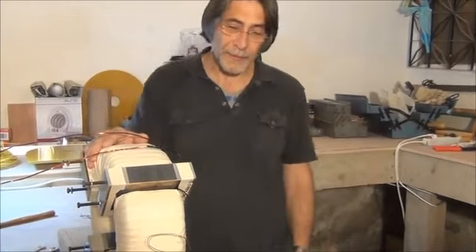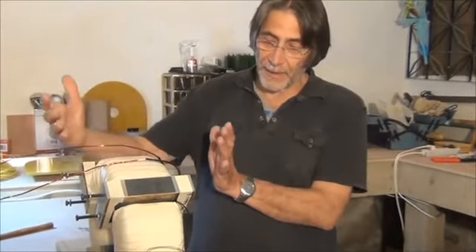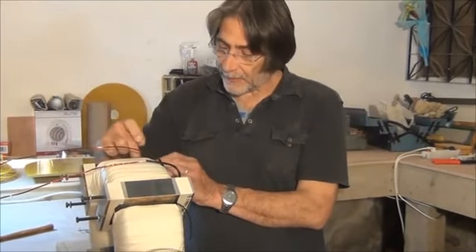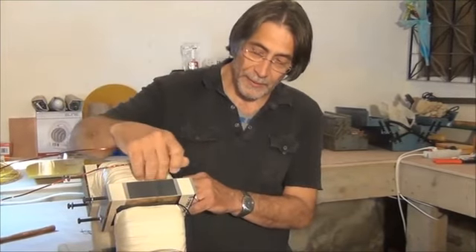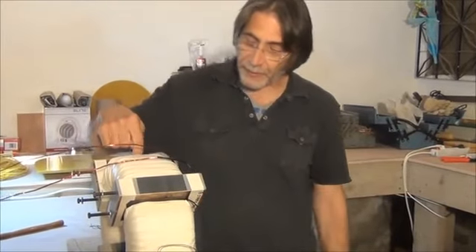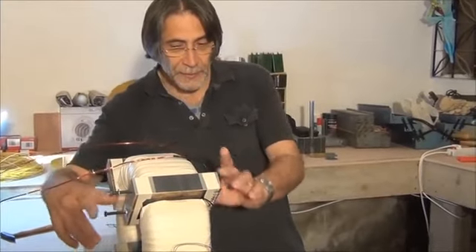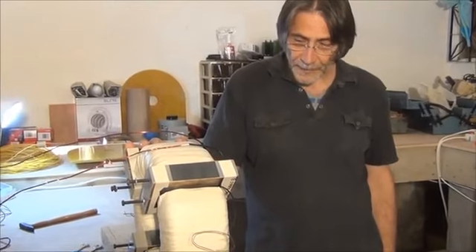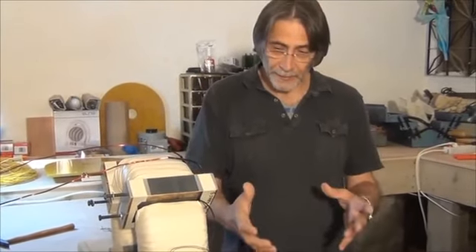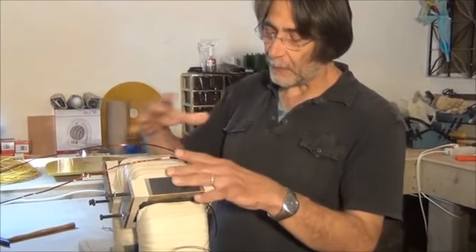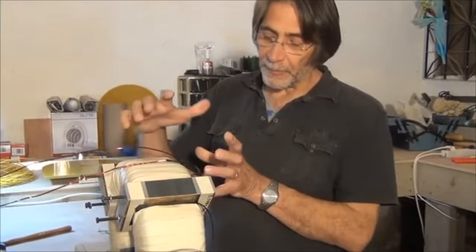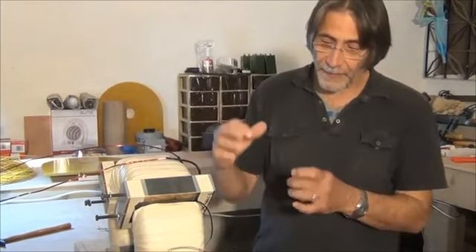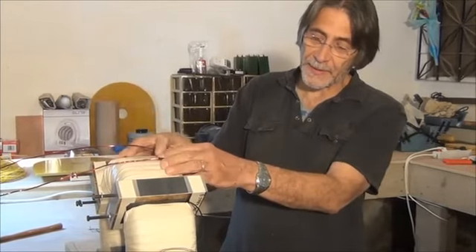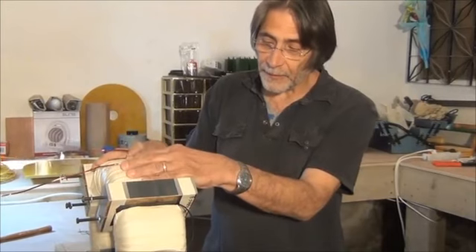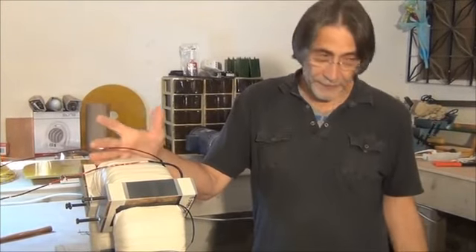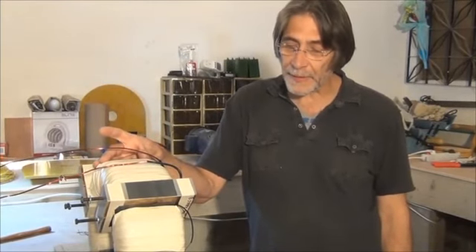The next cores that are built will have bobbins, a two-piece clamshell plastic bobbin that will cover the steel. And they're made to fit snugly right into the corners between the pole pieces and the main core. And we'll still have the mica plates, but they'll be sitting on top of the bobbin in the corners. And then the wire will be wrapped on the bobbins. And then they're going to do a vacuum epoxy impregnation. After the wire's put on the bobbin, there'll be a boot put on, and the boot will be filled with epoxy. And then they do a vacuum impregnation where they'll pull the air out and cause the epoxy to go right into the windings and fill for additional insulation. I'm told that that will double the insulation capacity.